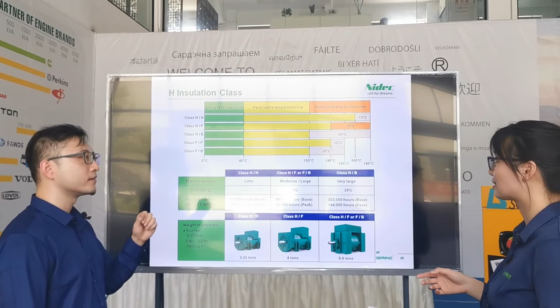If we have a winding with H class insulation, it will improve the service life of the alternator. In the catalog of the product, you can see classes like HH, HF, HB — one refers to insulation class, and one refers to temperature rise class.